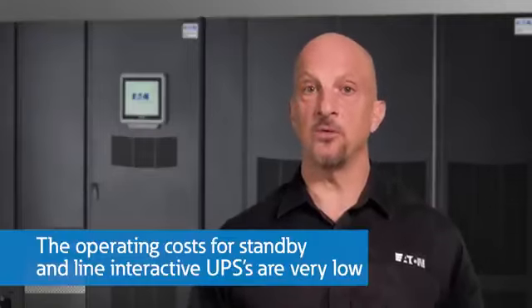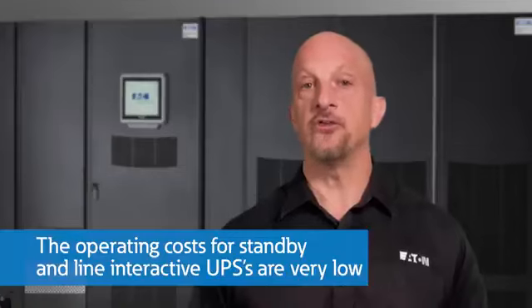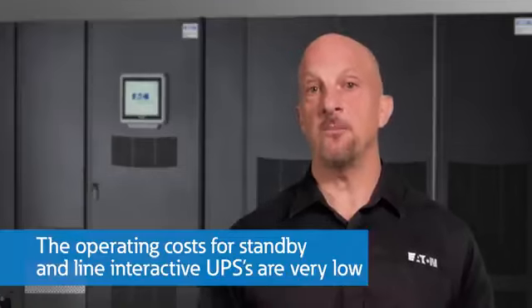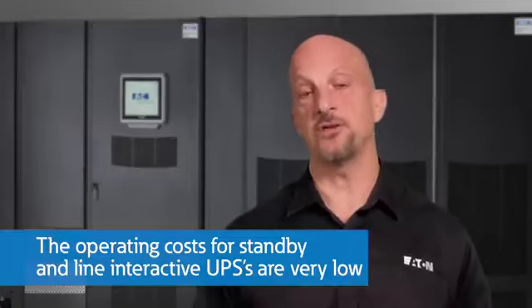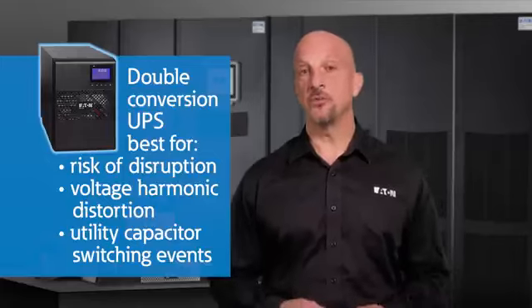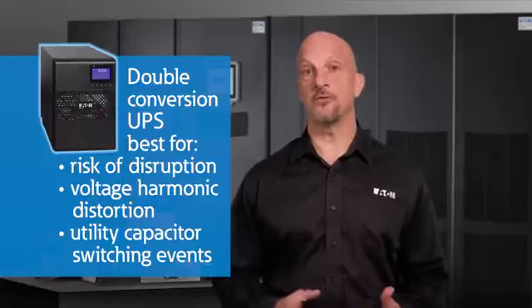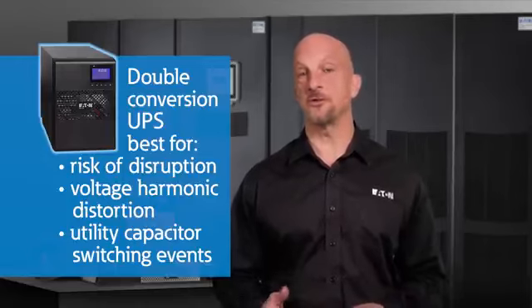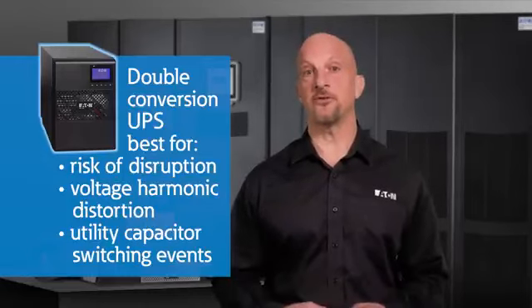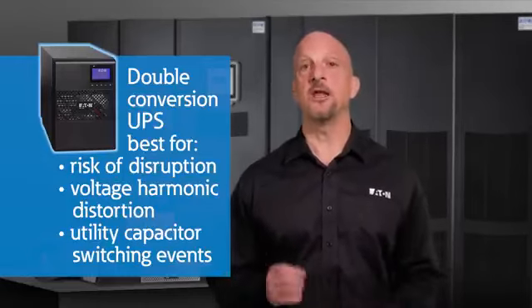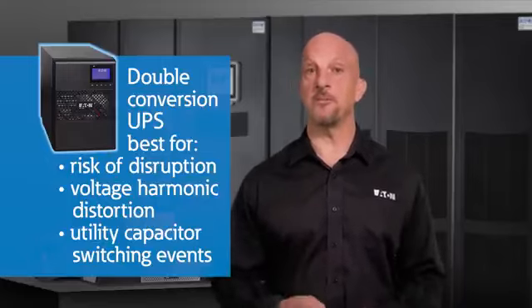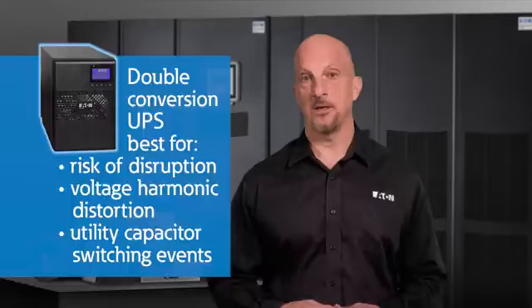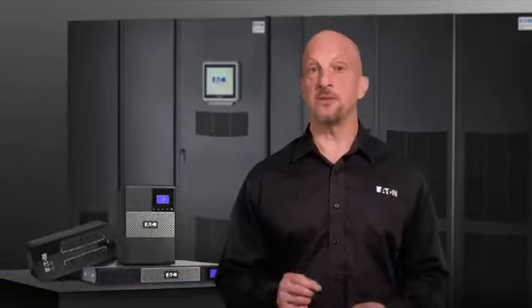For both the standby and line interactive UPSs, the operating cost, in other words, the cost of losses, is relatively very low and makes these a good choice for many applications. And finally, for situations where there's a risk of disruption from more extreme power quality situations like voltage harmonic distortion, utility capacitor switching events, or other issues, a double conversion UPS is probably the best option for your application. These are the considerations that you typically have to make for single-phase applications.